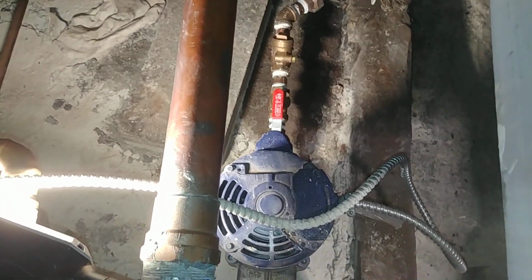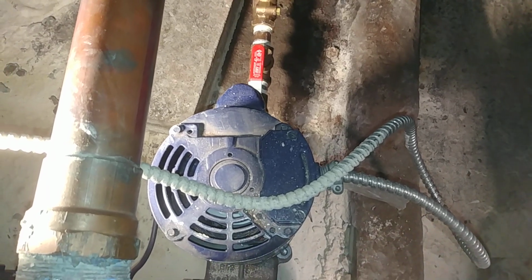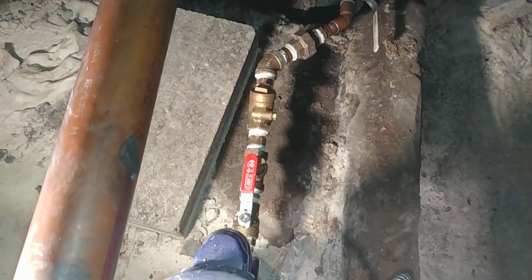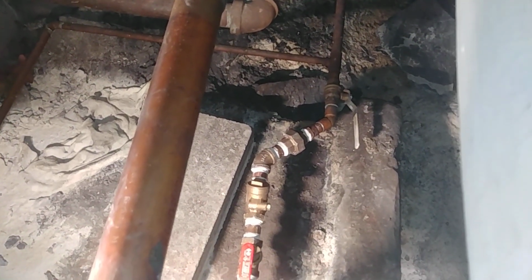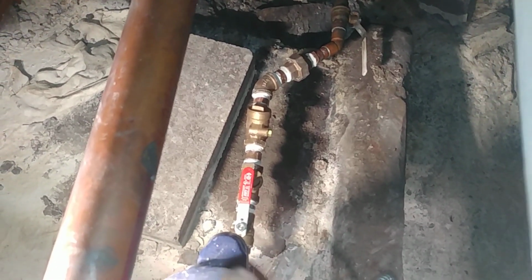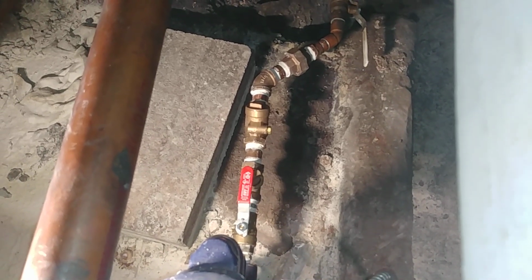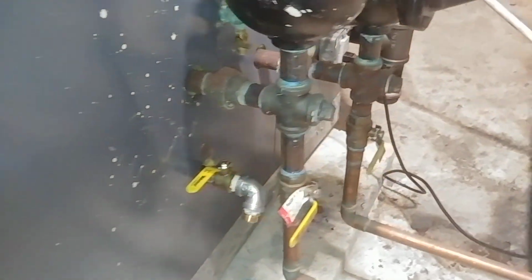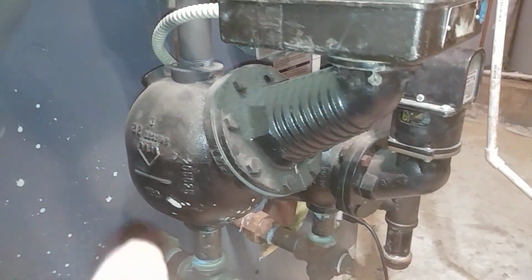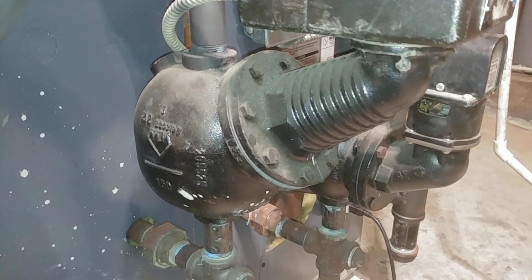What you are hearing is the feed pump on this boiler feed tank adding water to the boiler next to it through my slightly newly designed control mechanism there. It's receiving a signal to feed from this McDonnell & Miller float control. The float control was satisfied.